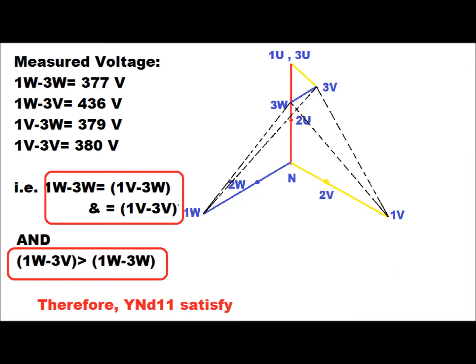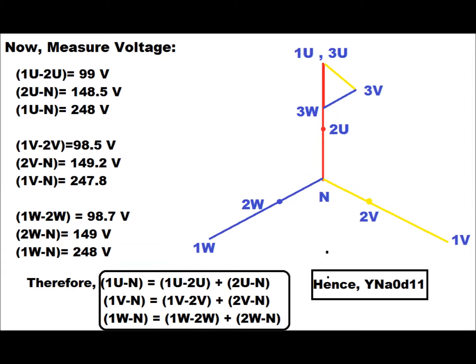Therefore the condition for YNd11 is satisfied. We then measure the voltage between 1U and 2U — primary red phase to secondary red phase — which comes to 99 V; between 2U and N, which comes to 148.5 V; and between 1U and N, which is 248 V. We can see that the primary red-to-neutral voltage equals the sum of the primary-to-secondary red phase voltage plus the secondary red-to-neutral voltage.